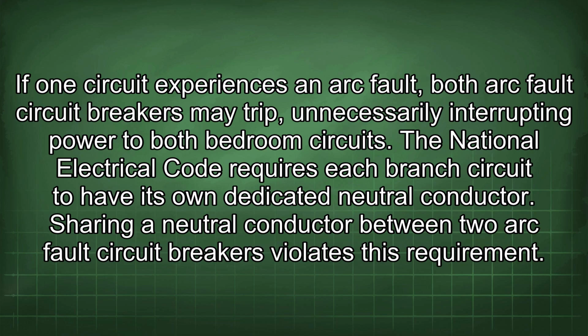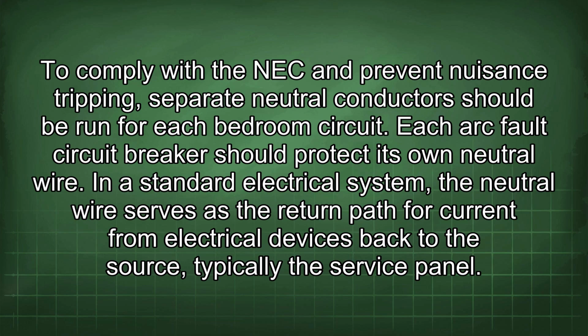Sharing a neutral conductor between 2 arc fault circuit breakers violates this requirement. To comply with the NEC and prevent nuisance tripping, separate neutral conductors should be run for each bedroom circuit. Each arc fault circuit breaker should protect its own neutral wire. In a standard electrical system, the neutral wire serves as the return path for current from electrical devices back to the source, typically the service panel.